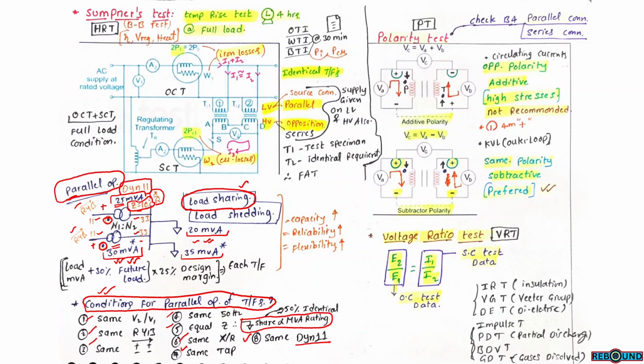In this case, the 25 MVA transformer and 30 MVA transformer both will share this 20 MVA load in proportion to their capacity. The load sharing depends upon impedance. For example, if we have two identical transformers, then the load sharing will be 50%. But here the ratings are different. One is a 25 MVA transformer, the other is a 30 MVA transformer. But the impedances are the same, X by R ratio also the same. Then the sharing is directly proportional to their respective MVA rating.